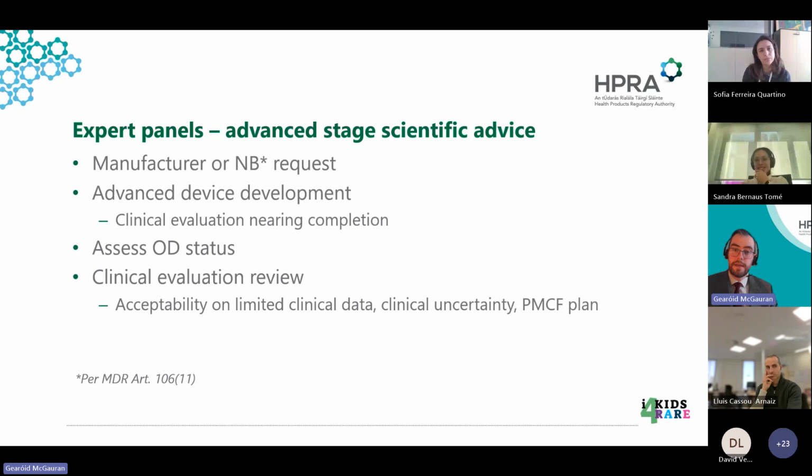Expert panels can also be useful in the more advanced pre-market stages, particularly with respect to giving scientific advice to notified bodies and manufacturers for legacy orphan devices. They can again provide support by assessing the orphan device status, as well as reviewing the clinical evaluation that's been done to date. They can give opinions on the acceptability of any limited clinical data and clinical uncertainty for the purposes of placement on the market, as well as give opinions on the acceptability of the manufacturer's PMCF plan to address and close out those limitations in the post-market setting.